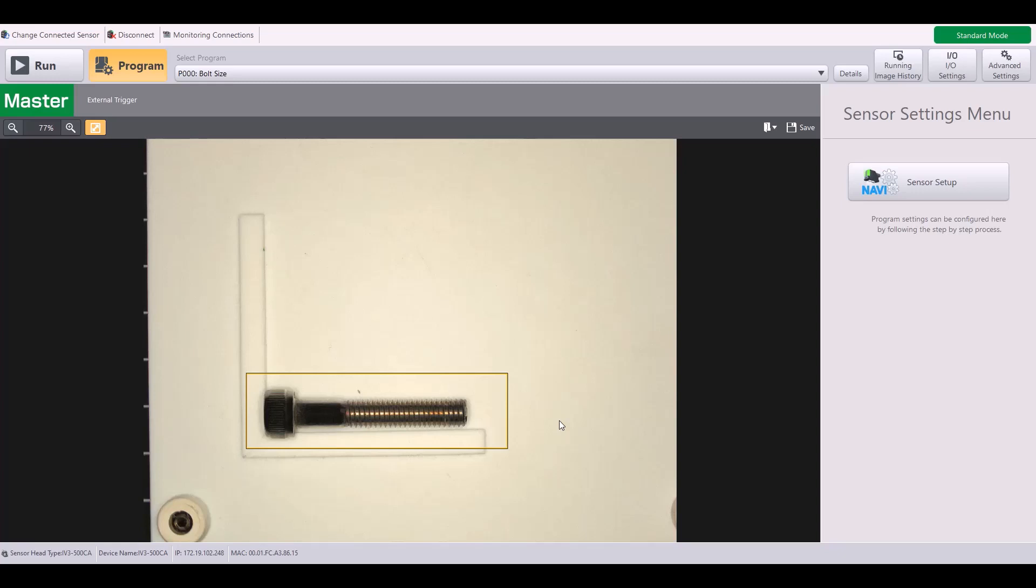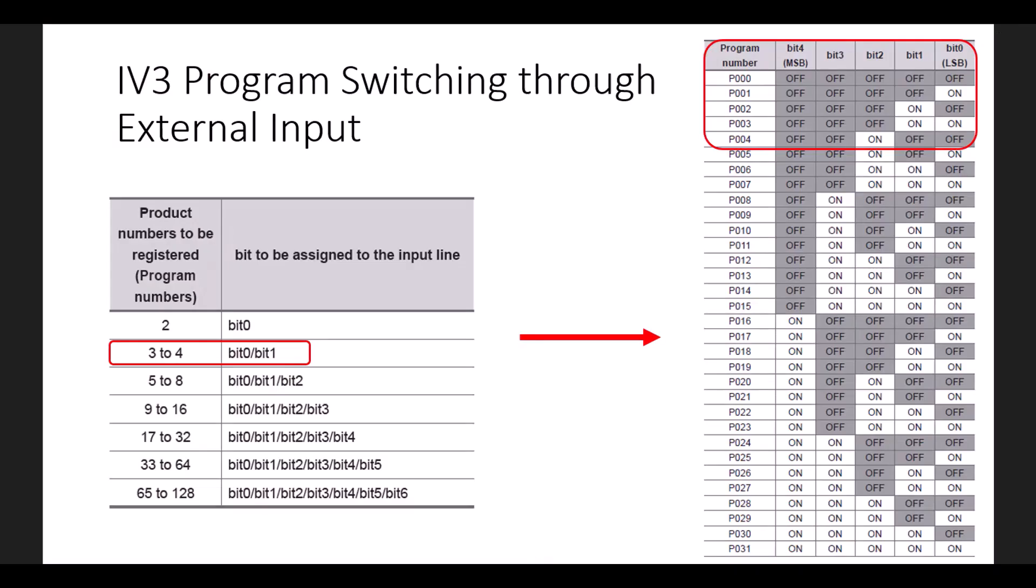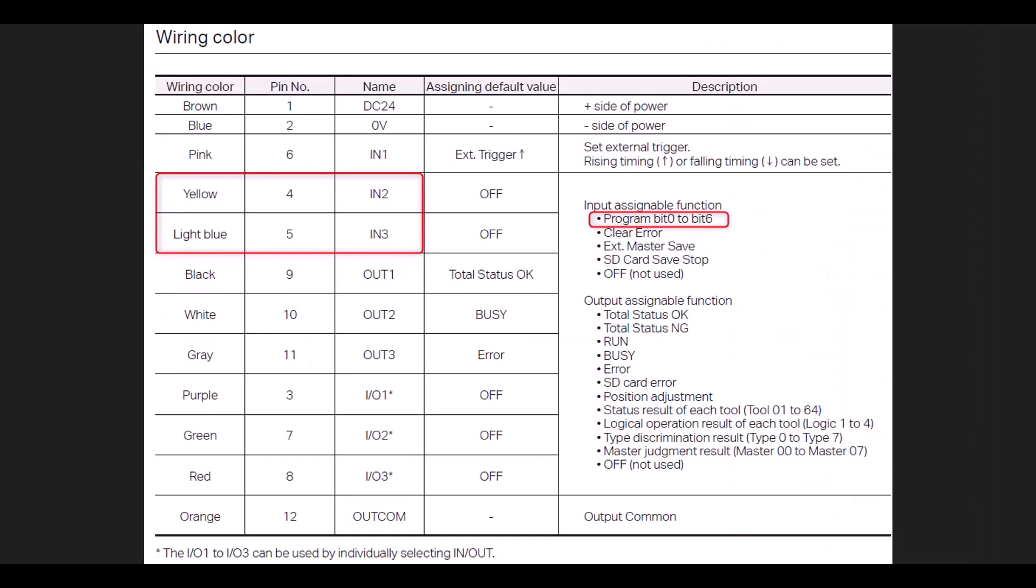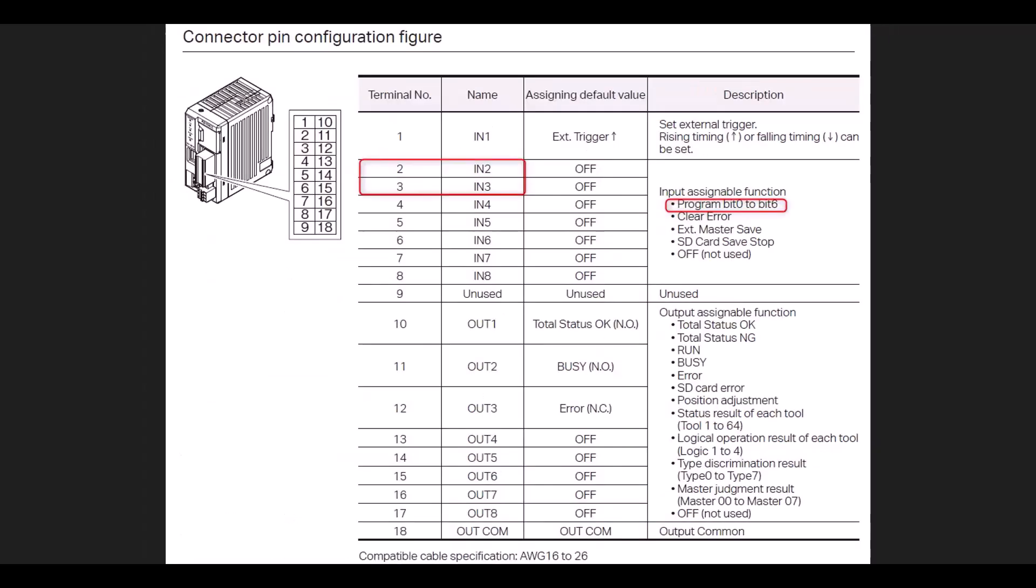And now we just need to consider which wiring on IV3 we need to be using. I'm using the self-contained model. So for input two and three, which is again what I assigned in the software, I'm going to be using the yellow and light blue wires. If you are using the IV3G model, which is the separate head and amplifier, you'd use terminals two and three for those two inputs.